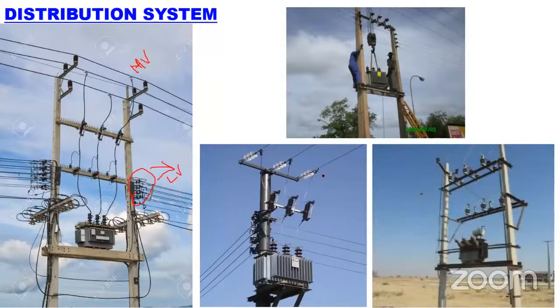Okay, so for the transformer bay, a fuse is always mandatory, because if there's any fault on the transformer, this fuse will blow out. When you say substation, a circuit breaker doesn't blow out - a circuit breaker will open and close in high current and high voltage applications. But in the distribution side, this fuse will blow out. This is basically ceramic and has a fuse link inside.